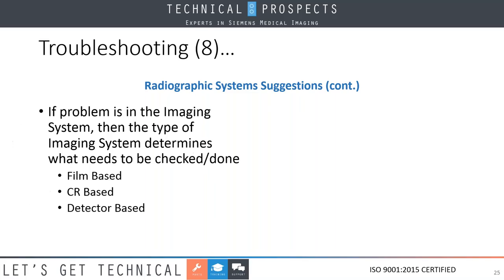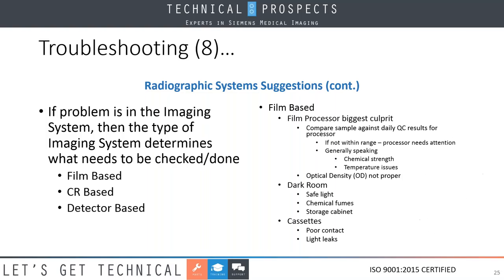Moving on from here, if it's in the imaging system, which system do you have? Again, I've provided some simple things for you to think about here. The biggest thing on a film-based system is the processor. Are they doing the daily QC? And is the chemical strength the same? Is the temperature good? We'll know that because the optical density isn't proper. How about light leaks in the dark room, cassette leaks?